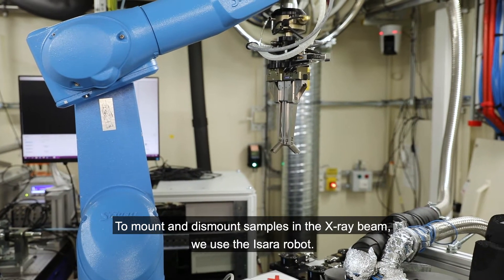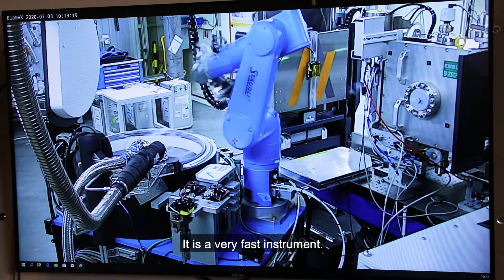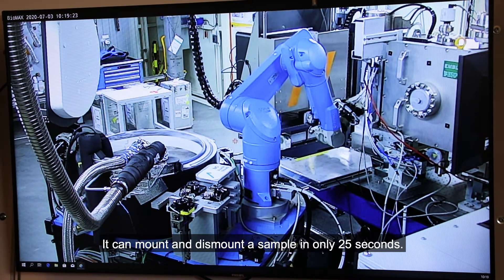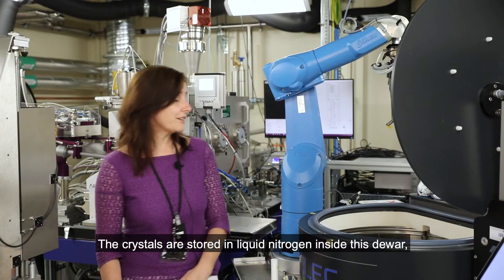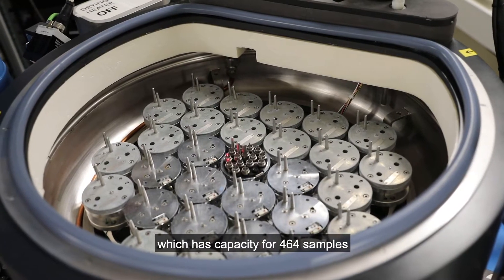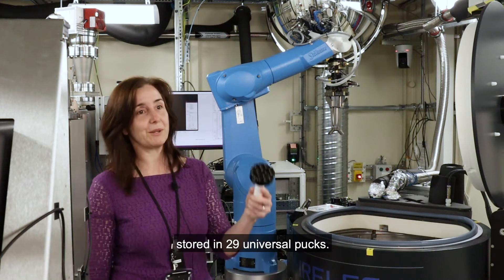To mount and dismount samples in the X-ray beam, we use the Isara robot. It's a very fast instrument — it can mount and dismount a sample in only 25 seconds. The crystals are stored in liquid nitrogen inside this dewar, which has capacity for 464 samples stored in 29 universal pucks.